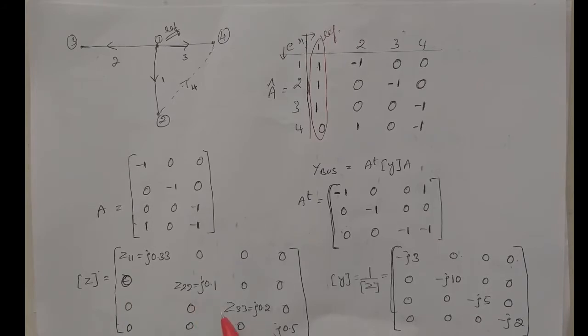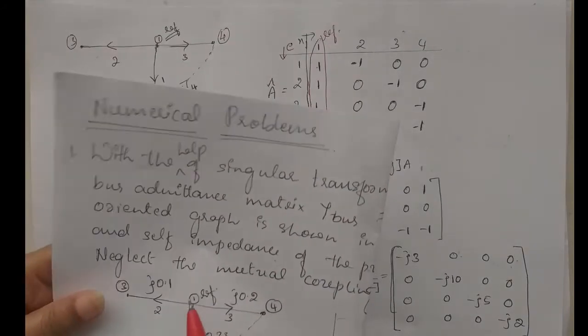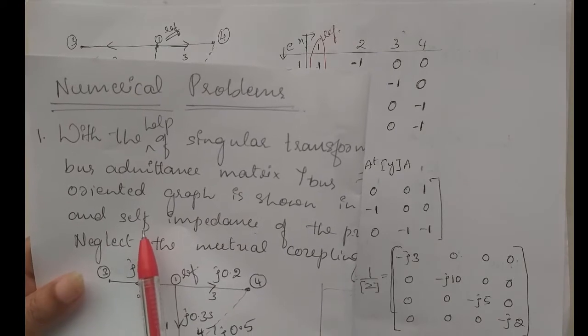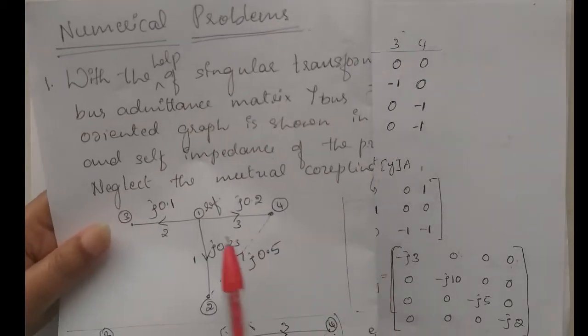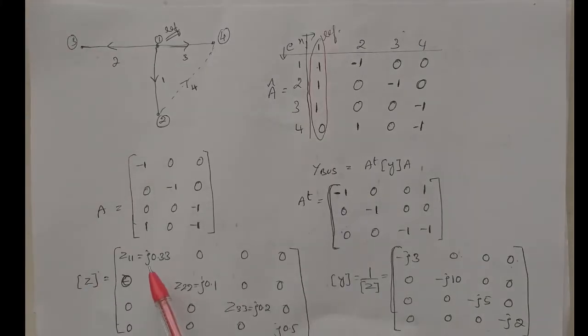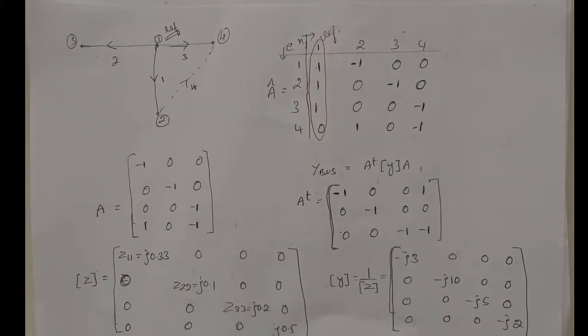It is a diagonal matrix because the given impedances are self-impedances. Here Z11, Z22, Z33, Z44 are the self-impedances, so it will be a diagonal matrix. Also, it is mentioned to neglect the mutual coupling. When we neglect mutual coupling, only the diagonal elements will be present and the off-diagonal elements will be zero. The reciprocal of this gives the Y matrix.